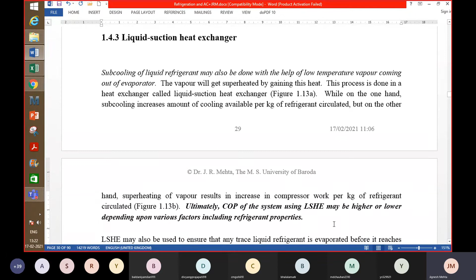The liquid that is coming out of the condenser, I'll go to the diagram. As it is written here, it is warm liquid. If it is an air cooled condenser, then obviously the liquid coming out of the condenser will be at a temperature slightly higher than the ambient temperature. Now this liquid can be subcooled in this heat exchanger, which we will call the liquid suction heat exchanger. The reason is that on one side there is liquid refrigerant, and on the other side there is suction vapor, that is the vapor which is entering the suction side of the compressor.